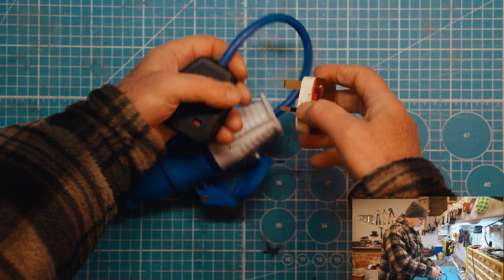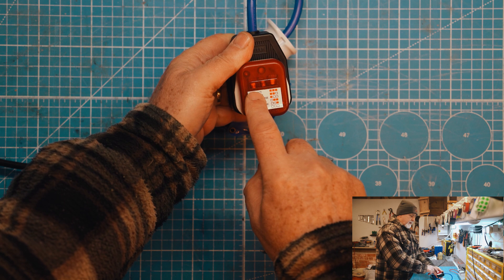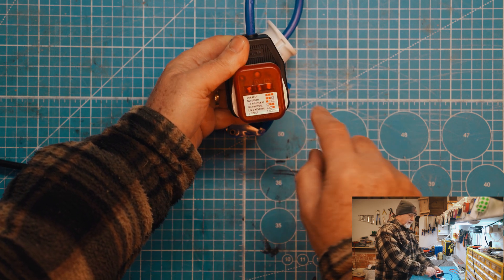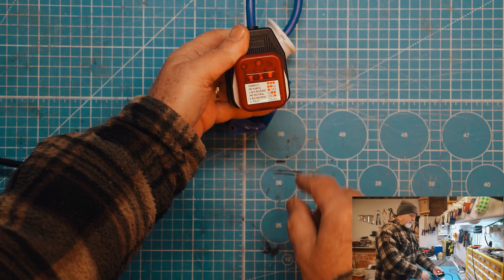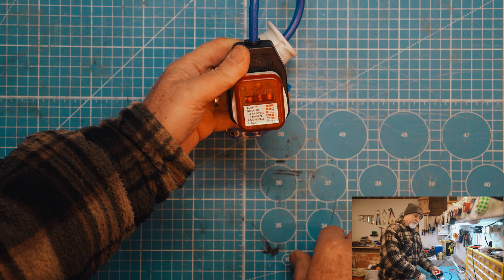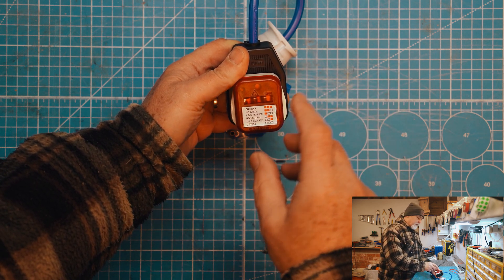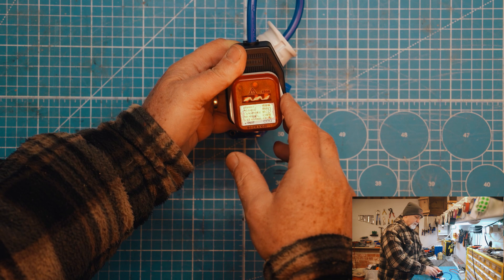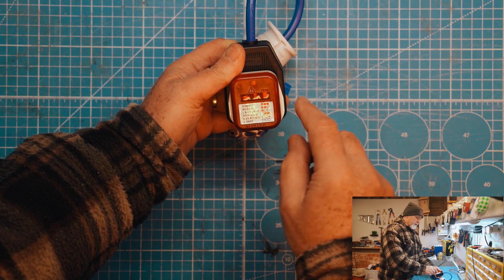So in this particular case, this one, to be correct, requires three red lights. You can see one, two, three. I'm seeing all three of them. So therefore, I know that the socket is completely to spec and safe. It's got its earth. The live and neutral are in the right places. So very happy with this.